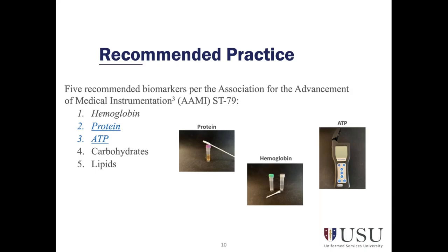Lastly, the hemoglobin-based system is an all-in-one test that indicates blood residues. The presence of blood in a surgical instrument indicates an inadequately reprocessed instrument and a source of cross-contamination. Hemoglobin testing is similar to protein testing. If any area of the swab turns green or blue, the surface of the instrument harbors blood residues and should be re-cleaned. To help clinicians and managers make an informed decision on which technology to adopt, AAMI has published a criteria that describe the elements that cleaning verification systems should have.